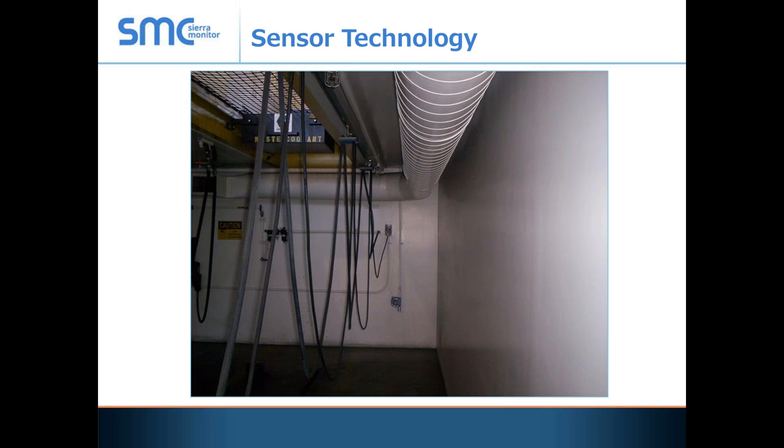There is a requirement when dealing with LNG vehicles maintained in these facilities: if you have a man pit — one that allows human access — you will have detection in those. The clarification was whether the pit was actually accessible by a human, because a lot of lifts are considered pits but aren't accessible. For an accessible walk-down pit, if you were to have an LNG release, the liquid would hit the floor and set that sensor off. That would trigger the shunt trip, cutting all electrical power and removing ignition sources, so you wouldn't have a catastrophic problem.